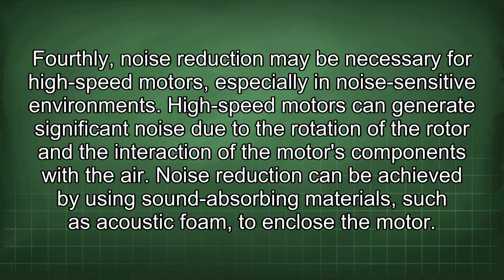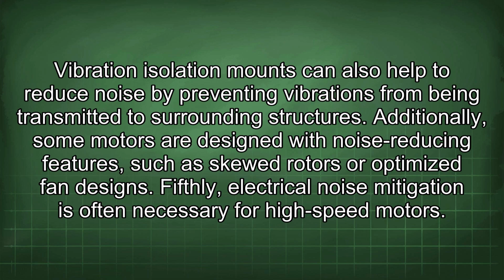Fourthly, noise reduction may be necessary for high-speed motors, especially in noise-sensitive environments. High-speed motors can generate significant noise due to the rotation of the rotor and the interaction of the motor's components with the air. Noise reduction can be achieved by using sound-absorbing materials such as acoustic foam to enclose the motor. Vibration isolation mounts can also help to reduce noise by preventing vibrations from being transmitted to surrounding structures. Additionally, some motors are designed with noise-reducing features, such as skew rotors or optimized fan designs.